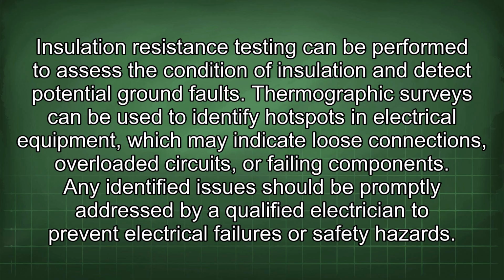Insulation resistance testing can be performed to assess the condition of insulation and detect potential ground faults. Thermographic surveys can be used to identify hotspots in electrical equipment, which may indicate loose connections, overloaded circuits, or failing components. Any identified issues should be promptly addressed by a qualified electrician to prevent electrical failures or safety hazards.